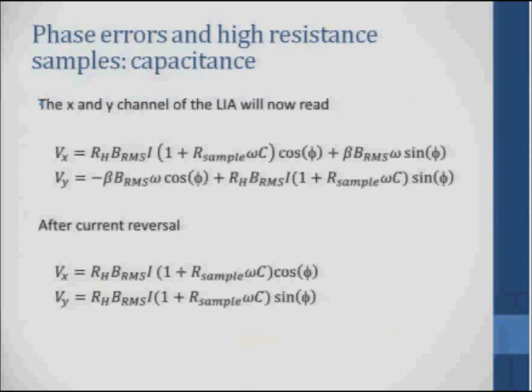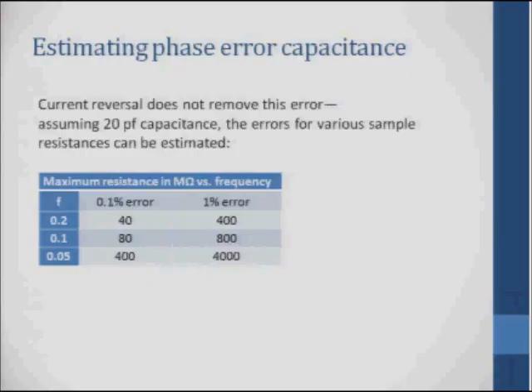This ultimately limits the accuracy of the measurement. If we assume about 20 pF capacitance in the cables, which is a pretty reasonable number, then for a 0.1% error at 100 millihertz frequency on the magnetic field, we'd be limited to about 80 megaohms. A 1% error would be about 800 megaohms. So this AC method is good to something like a gigaohm. Above a gigaohm, you're probably not going to want to use the AC method — you probably need to go back to the DC methods.